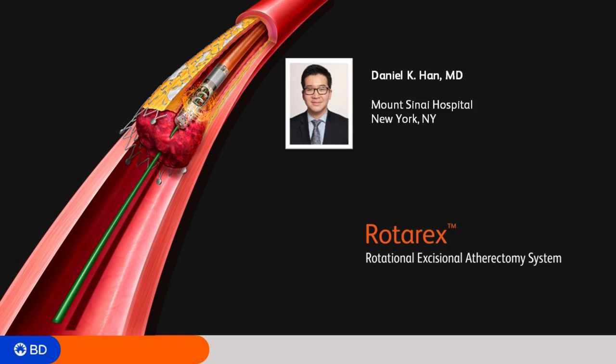Any advice for a new user? The biggest thing is using the 018 wire that comes with the kit. If you often use a filter wire, it may be a change from your practice, but Rotarex works better over a stiffer 018 wire that gives more support. Be patient — there is a lot of tactile feel, and you can see the blood entering the collection bag. Start from the top, move very slowly throughout the segment. Don't think in terms of passes; think of it as establishing flow from the top of the lesion all the way to the bottom.